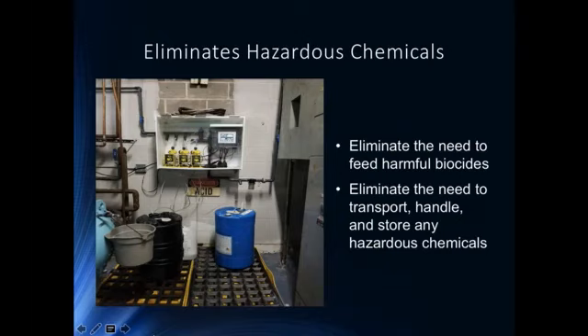As we talked, eliminating chemicals, this is a typical picture of what a control room might look like. Again, you've got chemicals there. In this case, we've got sulfuric acid. A lot of times there's secondary containment, sometimes there's not. Unfortunately, within a lot of our spaces, we are actually needing to bring these hazardous chemicals through tenant spaces or through tenant elevators or even through freight elevators. So the liability and the potential for contact continues to go up. And so by eliminating these, we make it much easier so that we can take care of it.